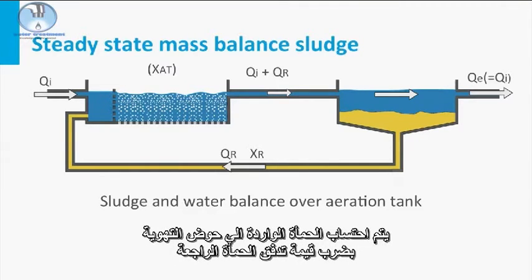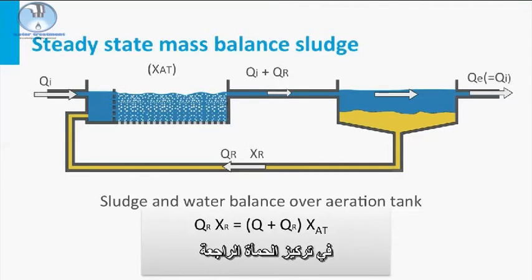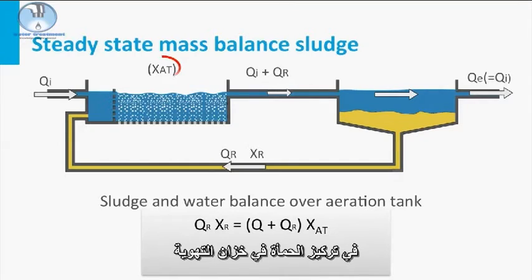Sludge entering the aeration tank is calculated by multiplying the return sludge flow times the return sludge concentration. Sludge leaving this tank is calculated by the influent flow plus the recycled flow times the sludge concentration in the aeration tank.